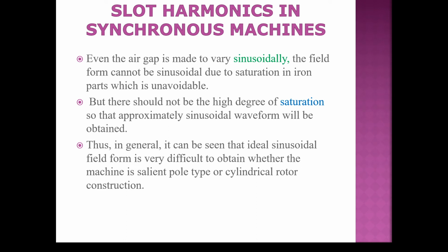Even if the air gap is made to vary sinusoidally, the field form cannot be sinusoidal due to saturation. To some extent we can make it, but due to the saturation in iron parts, which is unavoidable, the field cannot be made sinusoidal. But there should not be a high degree of saturation so that an approximately sinusoidal waveform will be obtained. So it can be seen that an ideal sinusoidal field waveform is very difficult to obtain, whether the machine is salient pole or cylindrical rotor type.